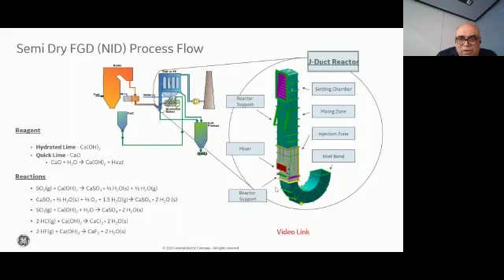If you look at the reagents, you are typically looking at lime, quick lime, or hydrated lime, and the reaction would basically be SO2 plus calcium hydroxide giving you calcium sulfite. Then part of the calcium sulfite would get converted to calcium sulfate. SO3 would also get captured in addition to HCl and HF, if there is any in the flue gas stream. Because most of the acid gases, that is HCl, HF, and SO3, are captured in the system, even though the system might be operating at a lower temperature, we do not see any issues related to corrosion in the existing stacks. That is why we typically talk about no modifications on the stack when it comes to semi-dry FGD solutions.